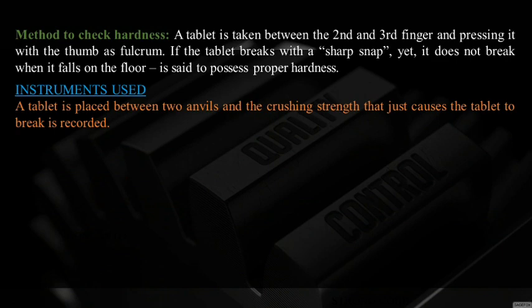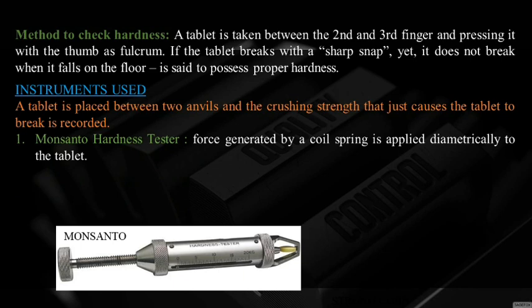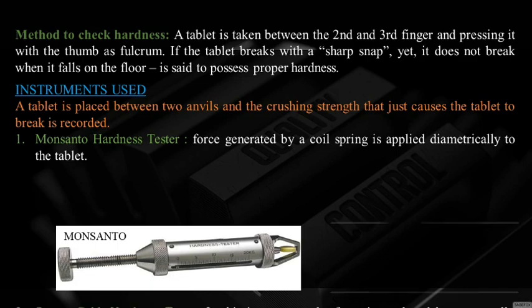For accurate measurement, a tablet is placed between two anvils and the crushing strength that just causes the tablet to break is recorded. The Monsanto hardness tester applies force via a coil spring diametrically to the tablet — it is the most commonly used and one of the earliest testers. The barrel contains a compressible spring held between two plungers; the upper plunger contacts the tablet and a zero reading is taken. The lower plunger is forced against the spring until the tablet fractures, and the pointer moves along a gauge in the barrel to indicate the force in kilograms.